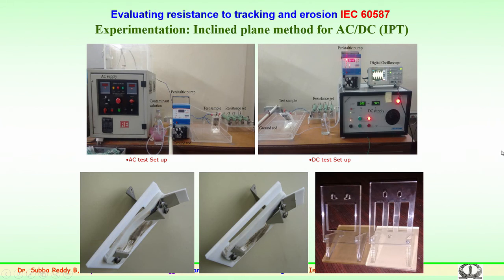For DC, the standard has not been evolved. For AC experimentation, the standard has been evolved. So these are the arrangements of the electrode. These are the electrodes. This is the sample holder and the sample which has been fixed at a known distance. In this arrangement, the Perspex sheet at a 45 degree angle, where the sample is mounted with the electrode arrangement, is shown here. This is how the fabrication has been done to make the sample and the arrangement as per the 60587 standard.